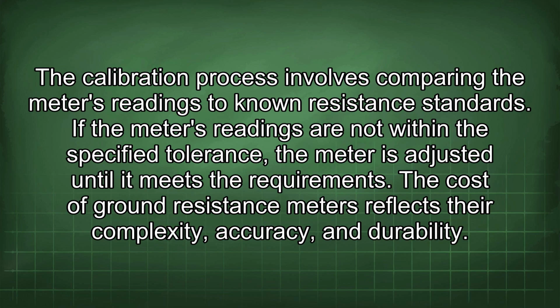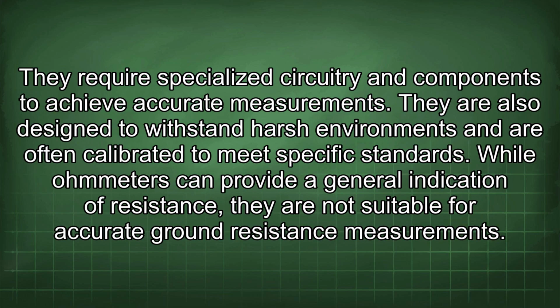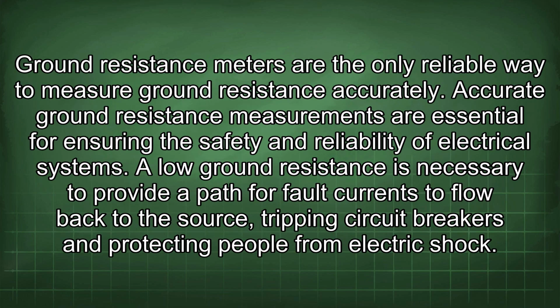The cost of ground resistance meters reflects their complexity, accuracy, and durability. They require specialized circuitry and components to achieve accurate measurements. They are also designed to withstand harsh environments and are often calibrated to meet specific standards. While ohmmeters can provide a general indication of resistance, they are not suitable for accurate ground resistance measurements. Ground resistance meters are the only reliable way to measure ground resistance accurately. Accurate ground resistance measurements are essential for ensuring the safety and reliability of electrical systems.